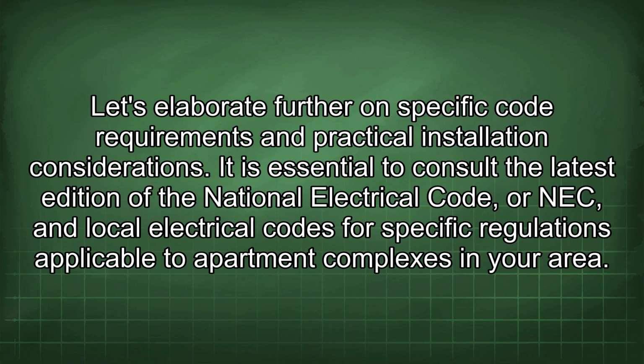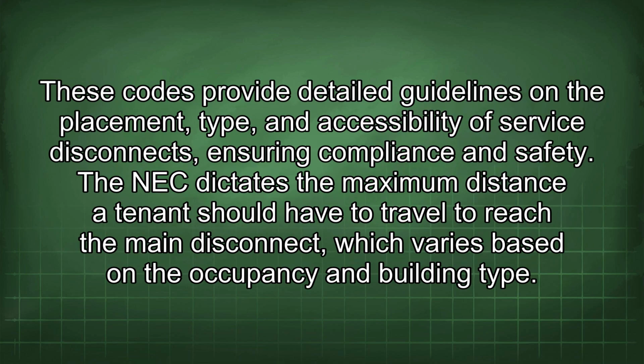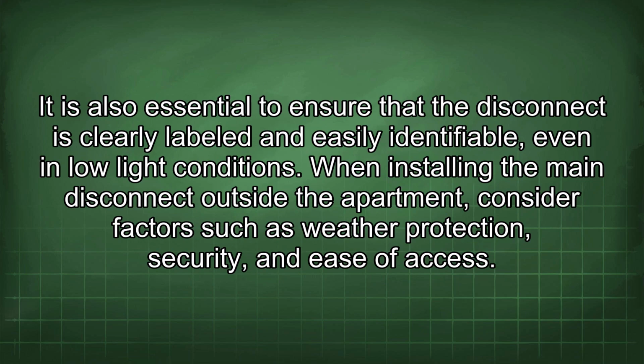Let's elaborate further on specific code requirements and practical installation considerations. It is essential to consult the latest edition of the National Electrical Code, or NEC, and local electrical codes for specific regulations applicable to apartment complexes in your area. These codes provide detailed guidelines on the placement, type, and accessibility of service disconnects, ensuring compliance and safety. The NEC dictates the maximum distance a tenant should have to travel to reach the main disconnect, which varies based on the occupancy and building type. It is also essential to ensure that the disconnect is clearly labeled and easily identifiable, even in low-light conditions.